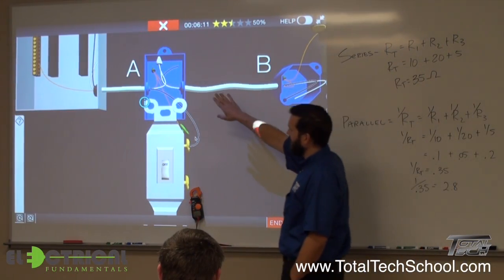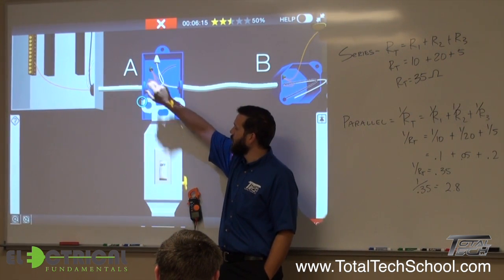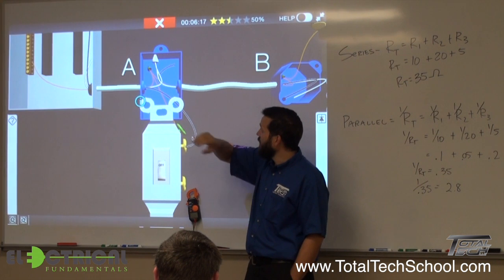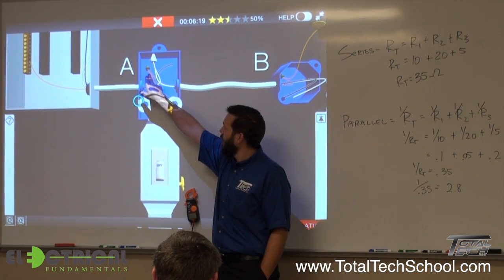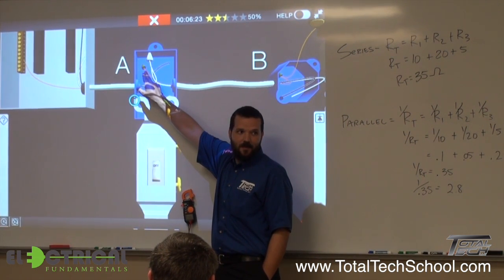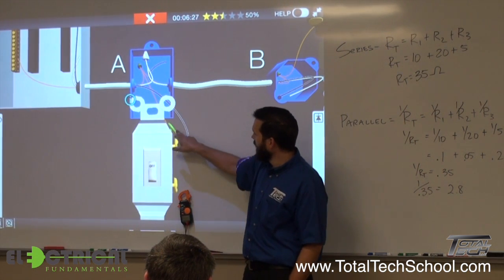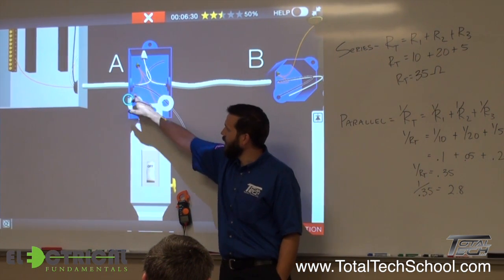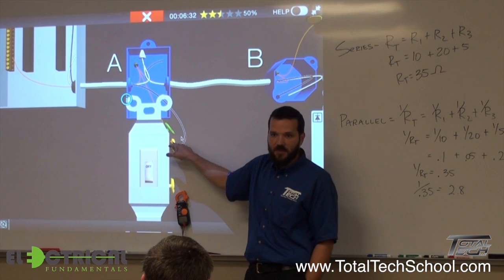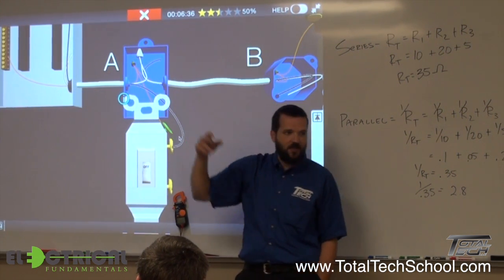Grounded conductor that we leave to future-proof this switch in case we bring in a digital device that requires that neutral. The reason they're doing that is because otherwise what tends to happen, and what I've seen in the field coming behind other contractors, is they pick up this equipment ground that is supposed to be bonded to this metal yoke to bond all the metal parts together. They just jump that off to pick up a neutral. And we discussed that yesterday.